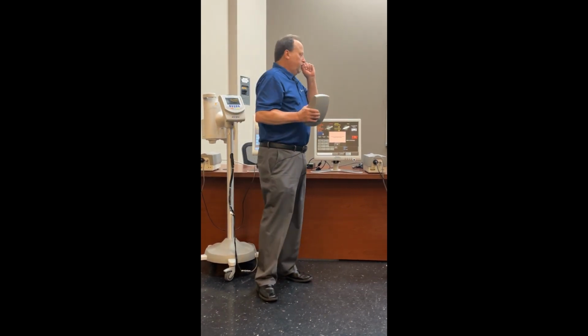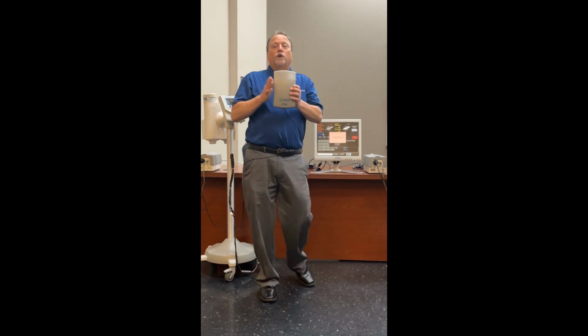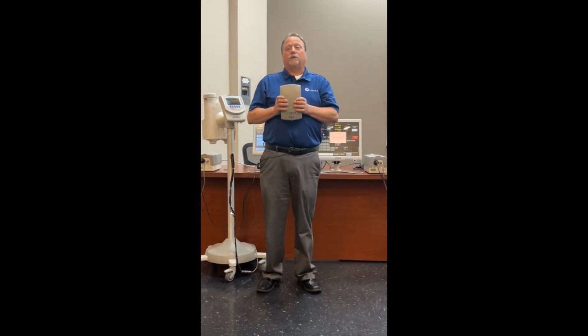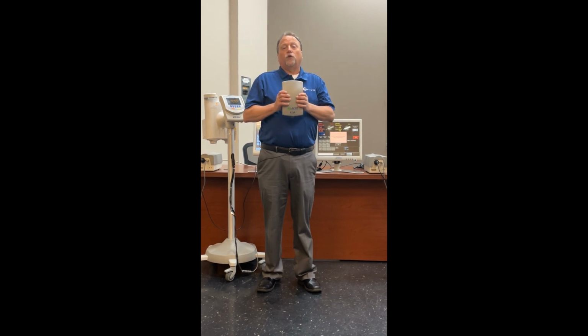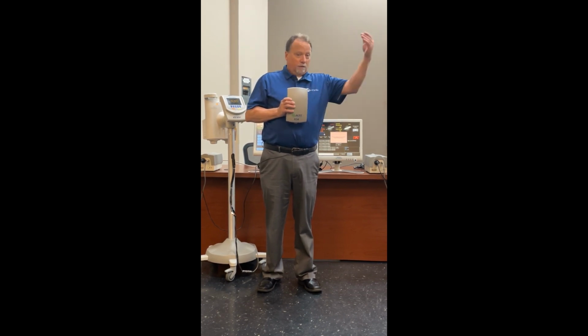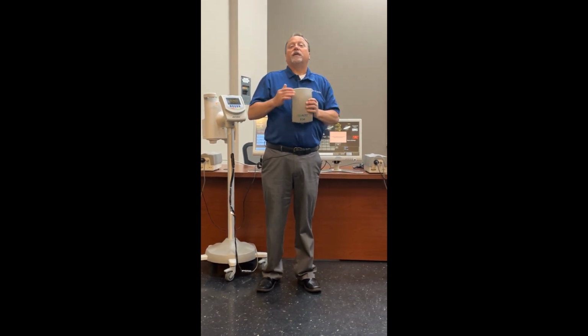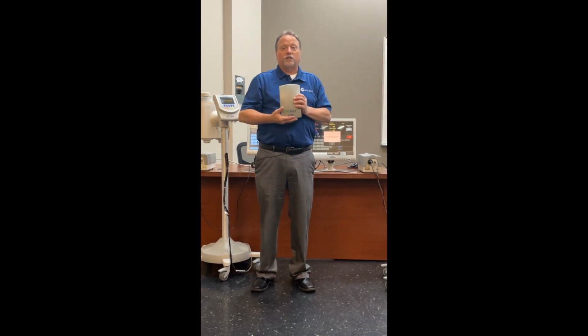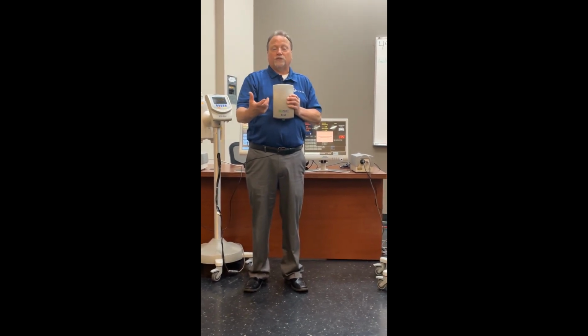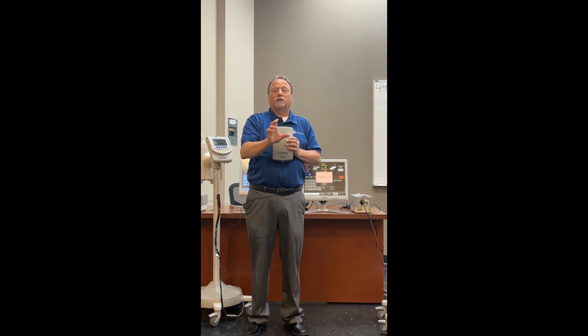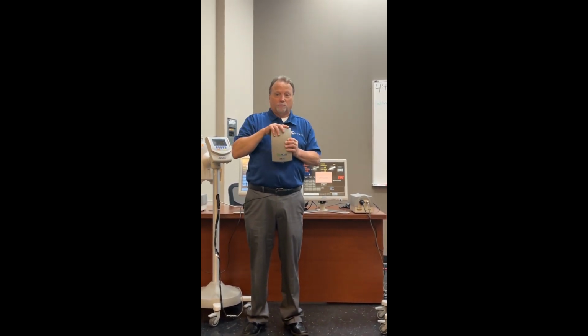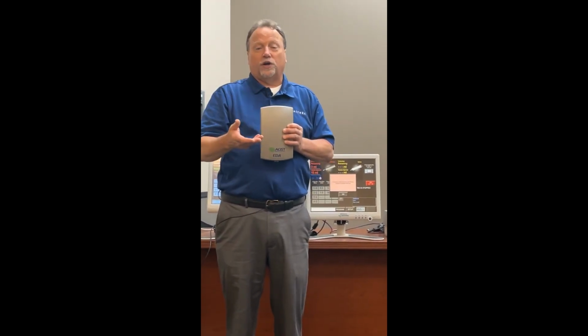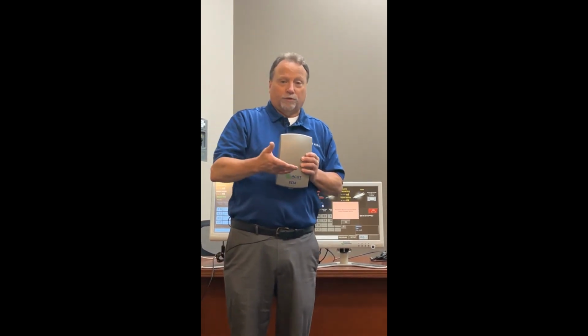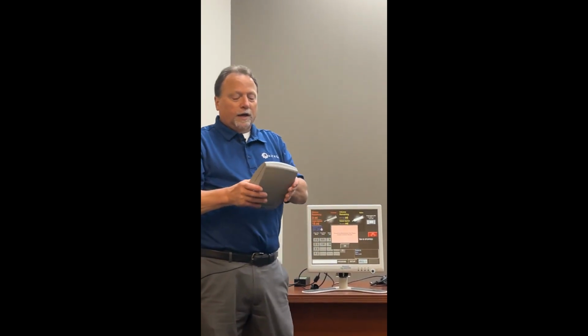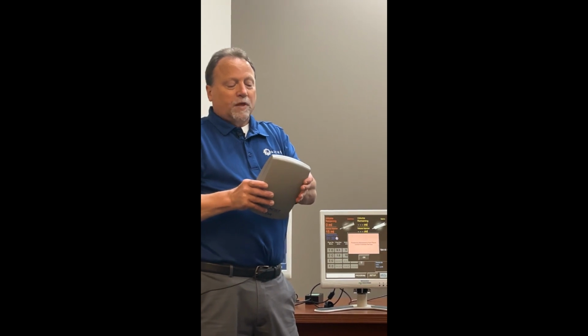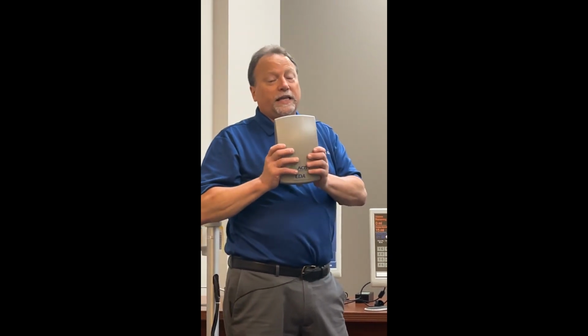Excuse me. We have developed, here at Althea, a module to not only do the same thing that the OEM module does, but even better. We connect it in, you use your meter for the resistance, and then you dial in what resistance you want to check this module out. And it's included in our Acist service kit when you come to training. They're used out there and they need to be checked.